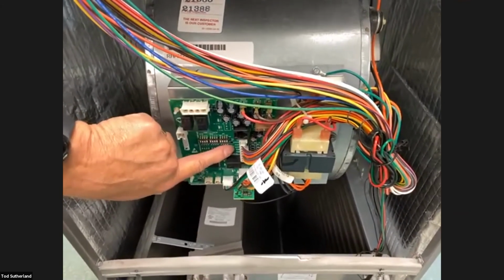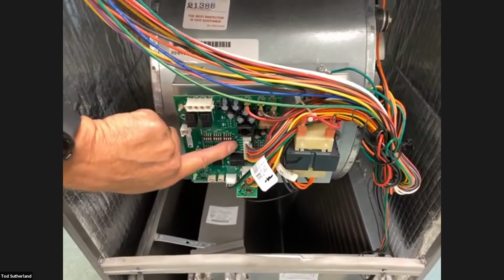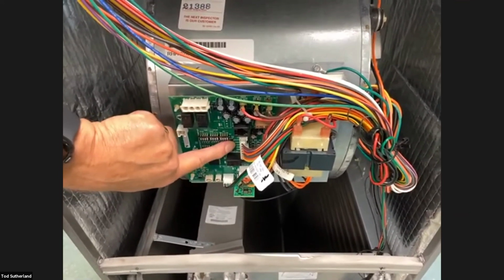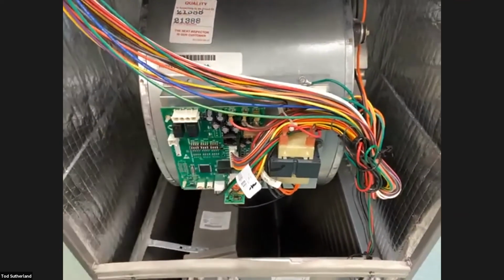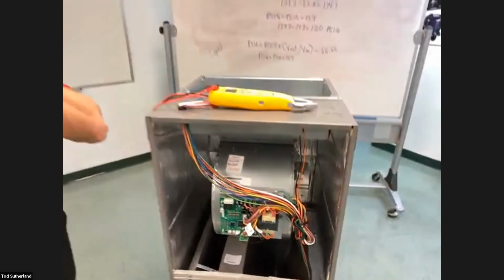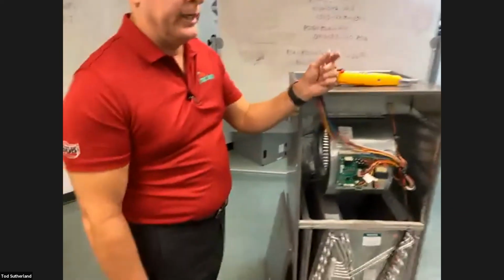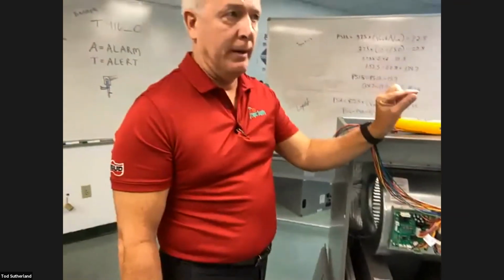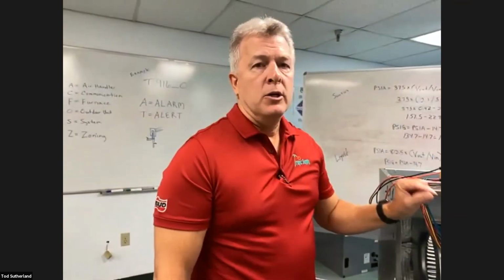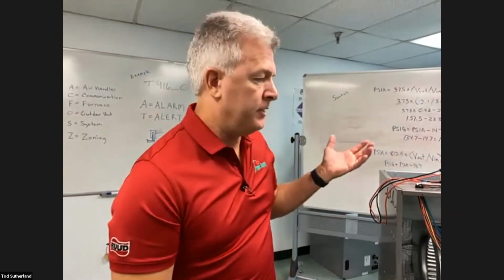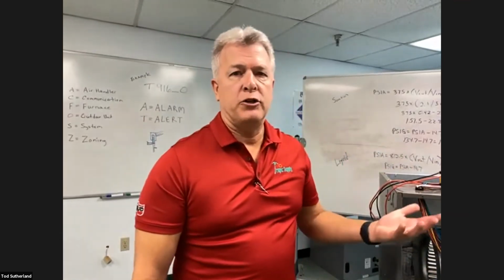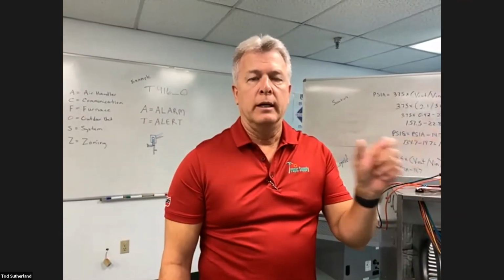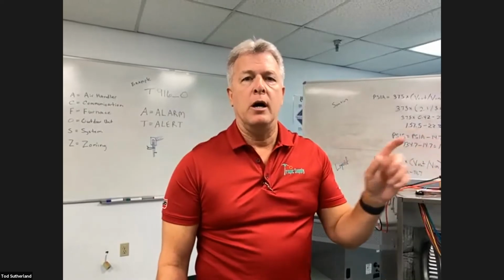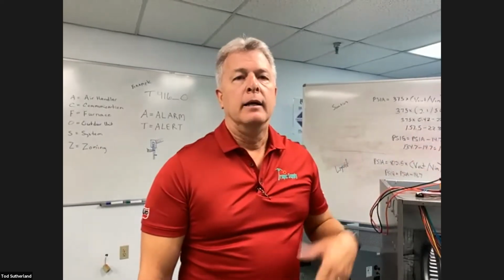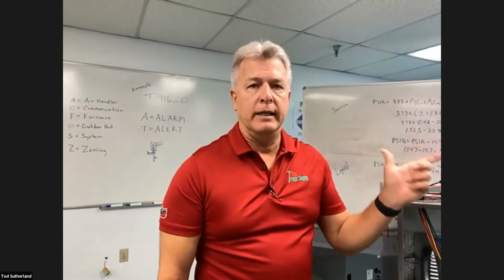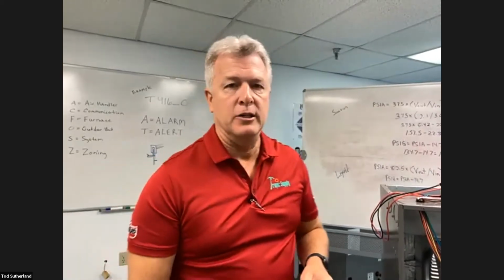So you'll simply take one side of your float switch and wire it to auxiliary C, and the second side to auxiliary 1. And then through steps in the Econet controller, you'll be able to find those auxiliary tabs and label them as float switch. So now, unlike your most conventional systems, if the float switch trips, it'll say float switch on the controller. So when your homeowner contacts you because their system's not operating, they'll be able to let you know that they have a float switch situation that needs to be addressed.